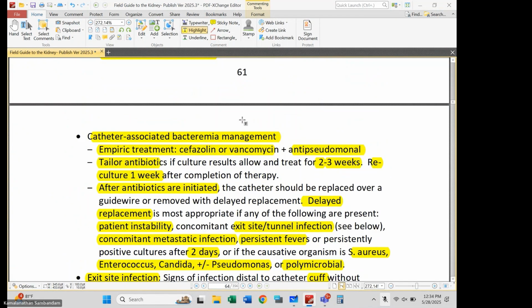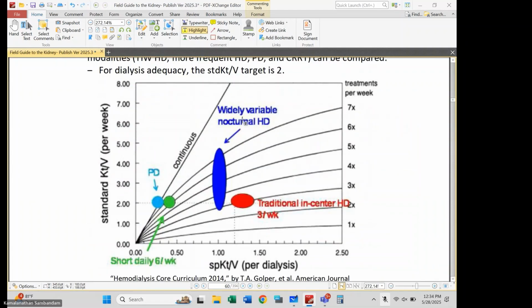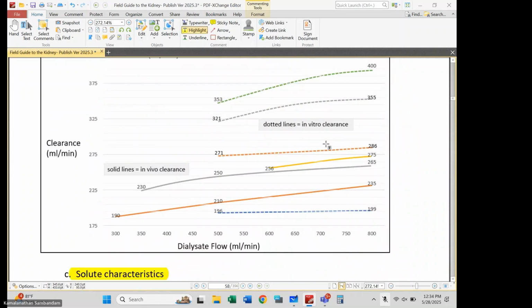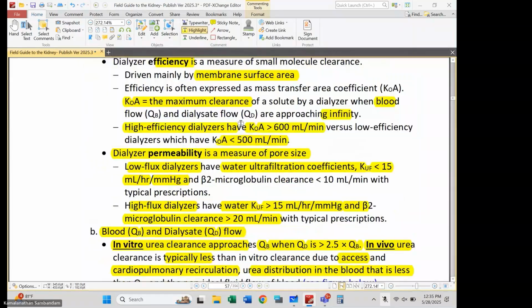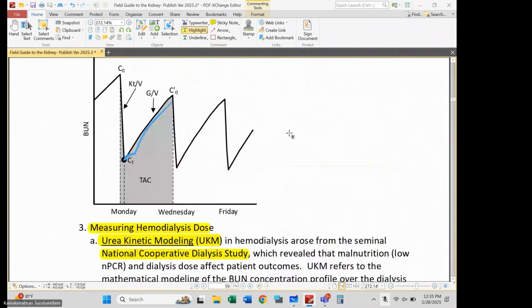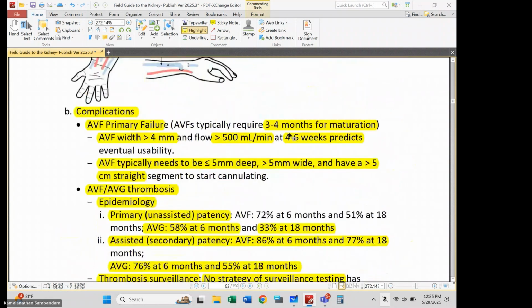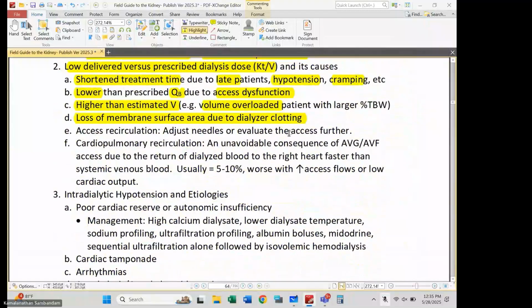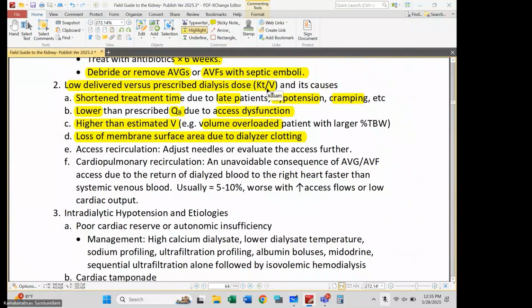What is the typical urea clearance? Remember, a typical urea clearance for dialysis would be somewhere around 300 mils per minute. What do these dialyzers give you? Well, they can have an effective urea clearance that's much more than 300. Typical high efficiency dialyzers have this mass transfer area coefficient. That's the maximal urea clearance that they can achieve. That's well above 300. So when you're clotting some of those capillaries, you're typically not meaningfully dropping K through loss of surface area, but you may have problems with time or lower blood flows as that dialyzer is clotting and pressures are rising.